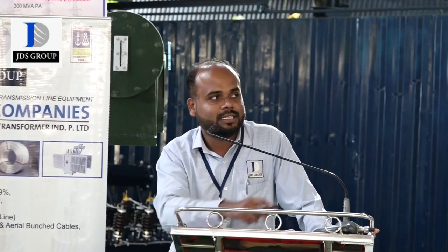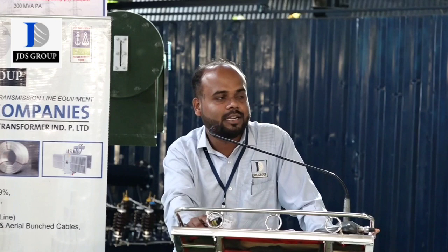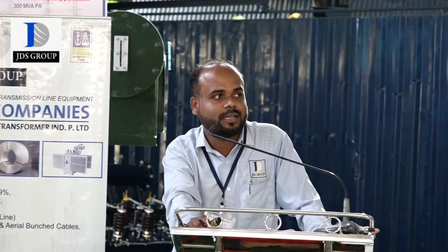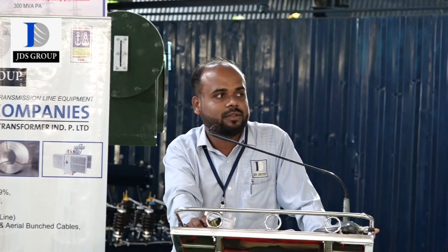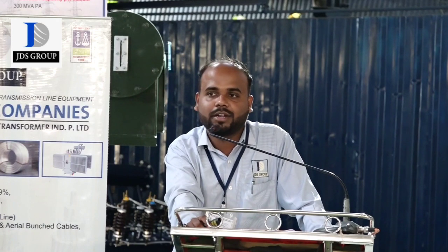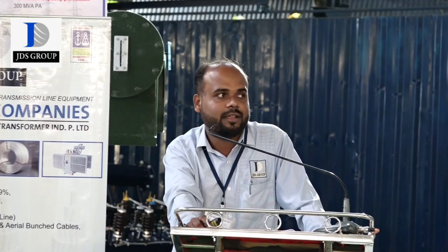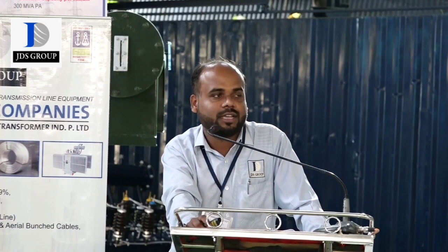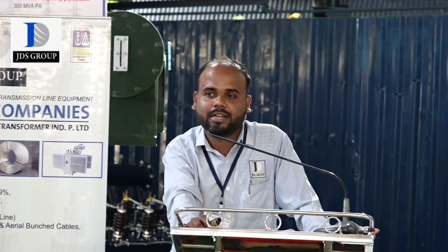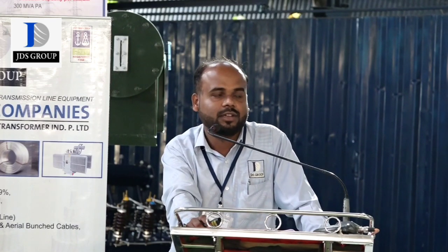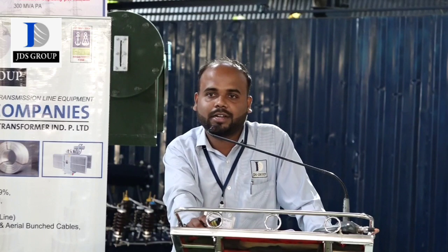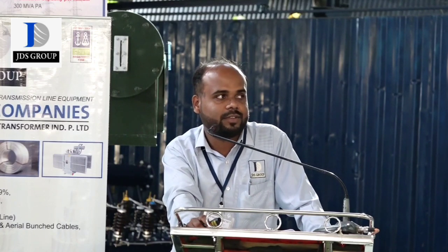And the second image is the representation of CCA, core coil assembly. From 16 kVA to 200 kVA we use aluminium wire, and for LV side we use LV strip, rectangular conductor, and for HV side we use round conductor. Above 200 kVA we use copper wire for HV side.